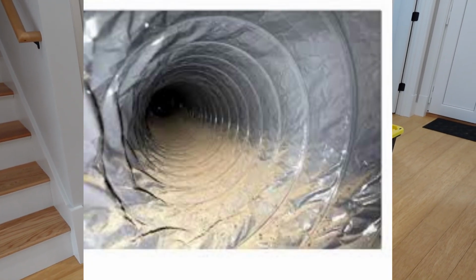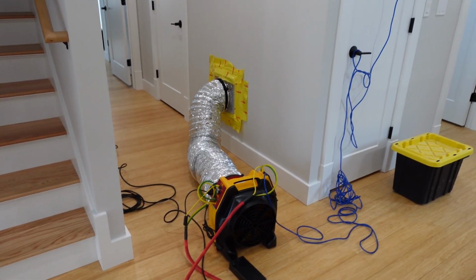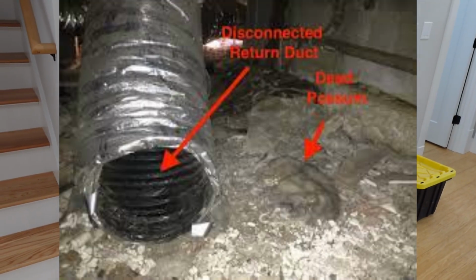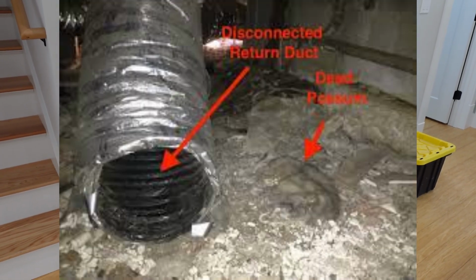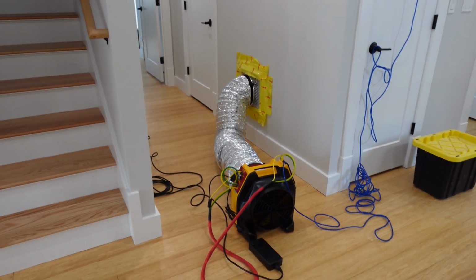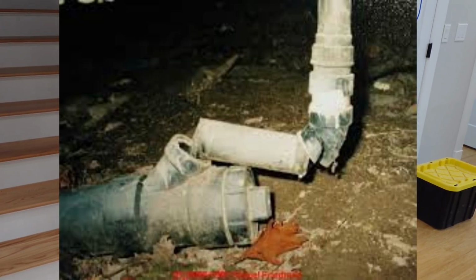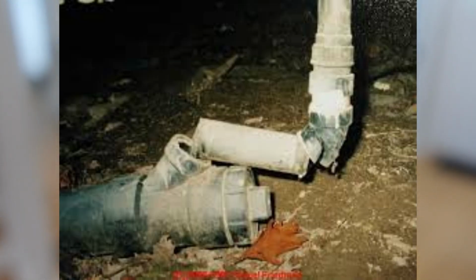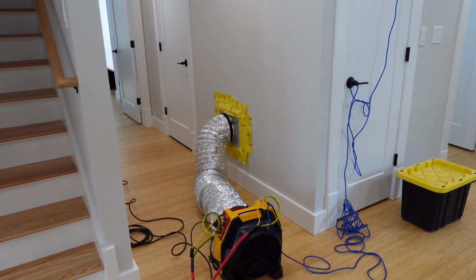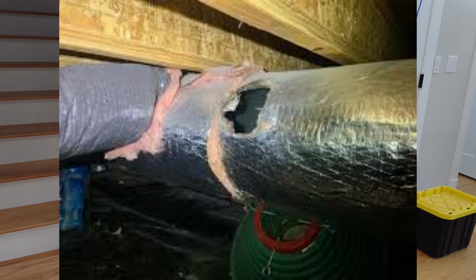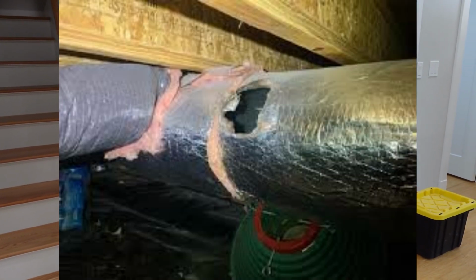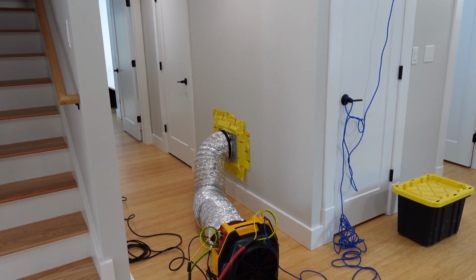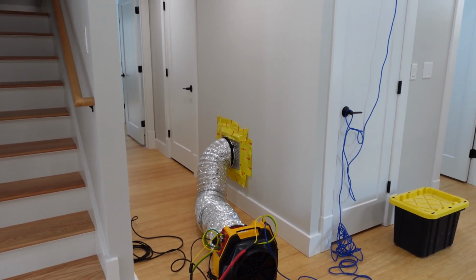So if you're in a basement that isn't conditioned, or a crawl space that isn't conditioned, and the cold air return is inside of that space, you could be sucking a lot of dust, debris, pollen, particulate matter, VOCs, chemicals, all of that stuff into the system, which is obviously going to push it inside of the home. So indoor air quality is part of it. Another reason is energy efficiency. Another reason is equipment longevity.